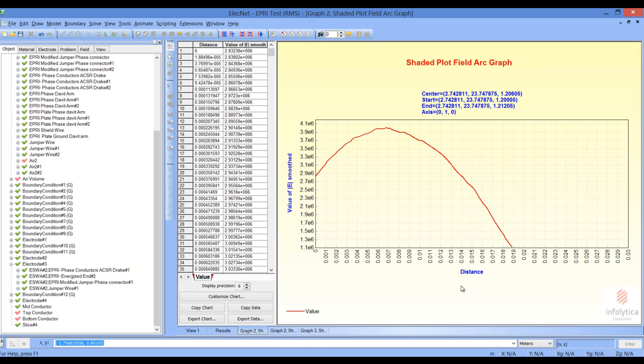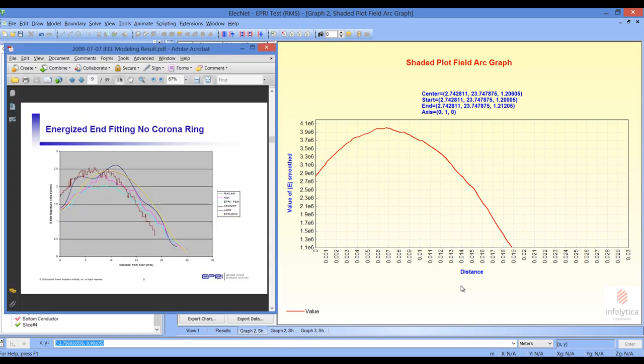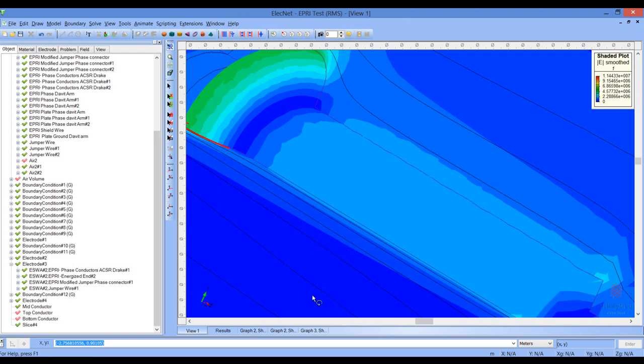We can also compare that to what was given in the results document from EPRI. One thing you'll note is that the maximum field value in this view is actually quite a bit higher than in the EPRI document. One of the reasons this is happening is that we now have interaction between the various other phases of the transmission line, which is bringing up the maximum value here.